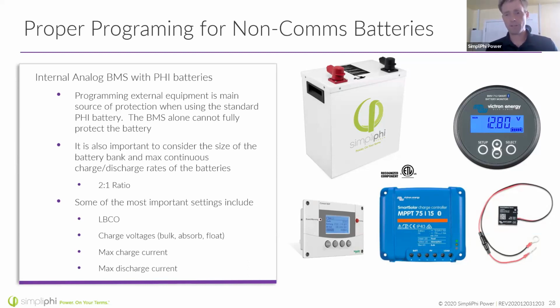And for our LFP battery chemistries, we don't have specific numbers from our engineering team on cycles depending on the top of the charge cycle. It has a much greater impact on the bottom side of the charge cycle. So for LFP batteries, we have to worry more about what we're discharging to. That being said, no batteries like being charged above the voltage that they should be set at. We should not have any voltages above 56 volts for our 48 volt battery nominals, and you should not have anything above 28 volts for our 24 volt batteries. So hopefully I answered that question. We don't have a preference for only charging up to 90% state of charge for our batteries because they're LFP, not NMC. But on the discharge side, it does make a difference, the depth of discharge.